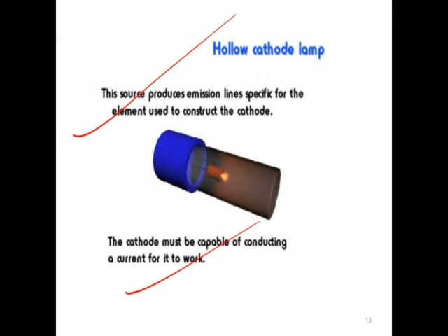So the hollow cathode lamp is the radiation source. The hollow cathode lamp is the most common source in atomic absorption spectroscopy. So what does this lamp consist of? It consists of a glass tube, and this glass tube is filled with gases, either neon or argon. These are inert gases. Then the cathode is a cylindrical metal cathode containing the metal for the excitation, and an anode. So the metal is present on the surface of the cathode.